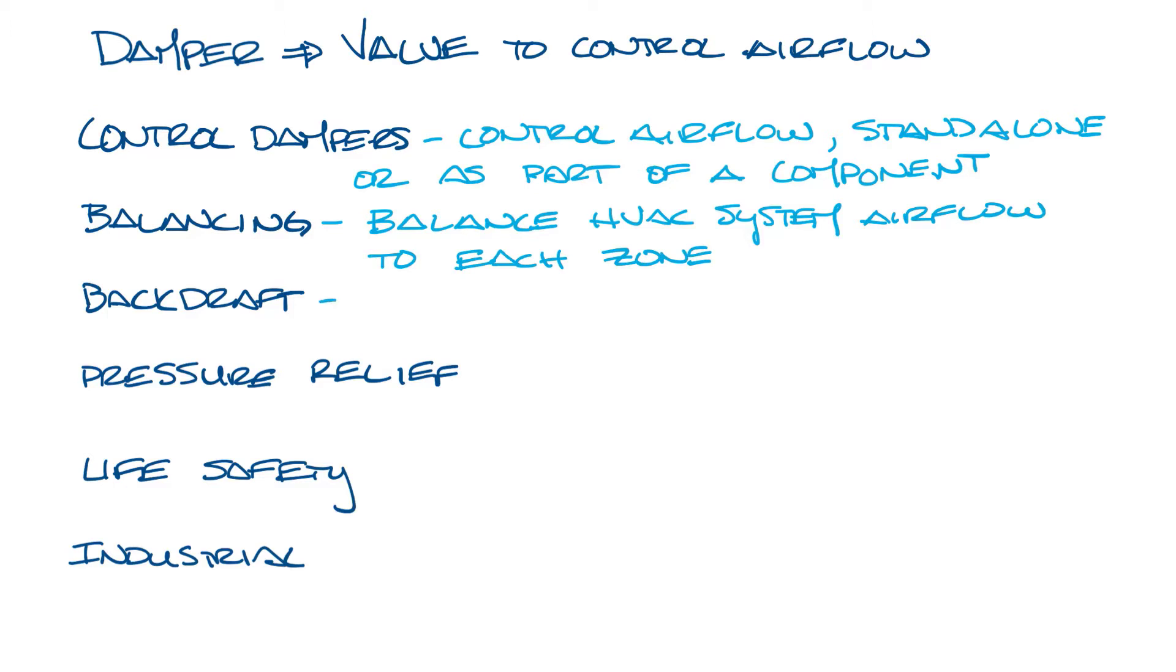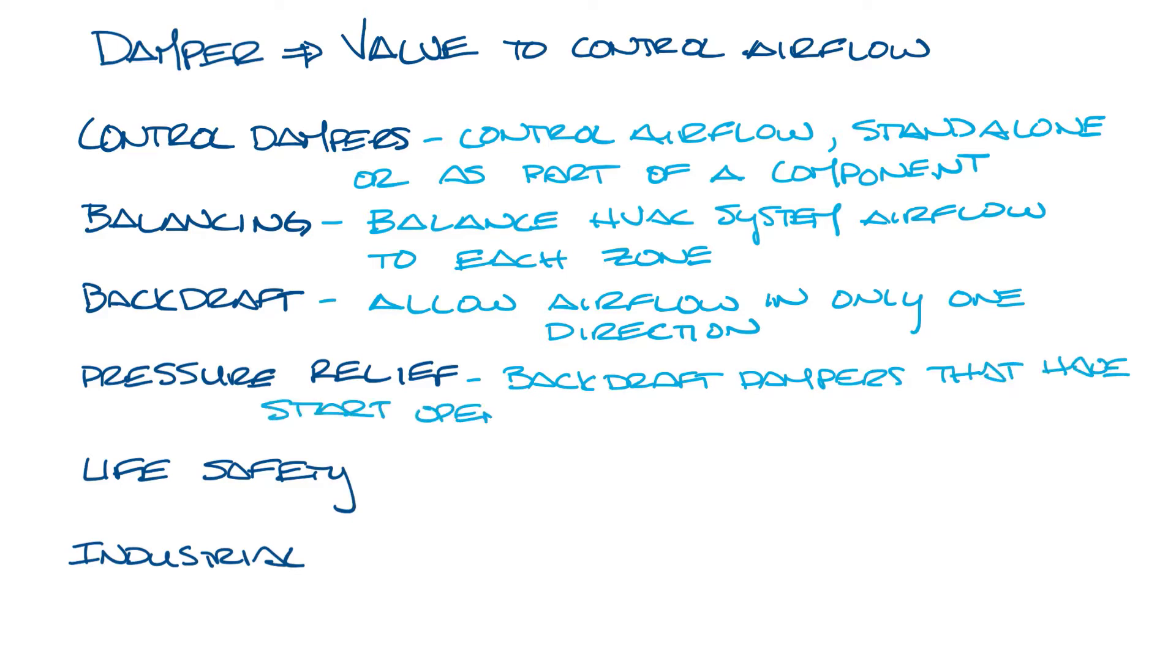Backdraft dampers allow airflow in only one direction to prevent backdrafts. Pressure relief dampers are backdraft dampers that have a start-open pressure so that if the pressure exceeds that predetermined point, the damper will open and allow the pressure to be relieved.